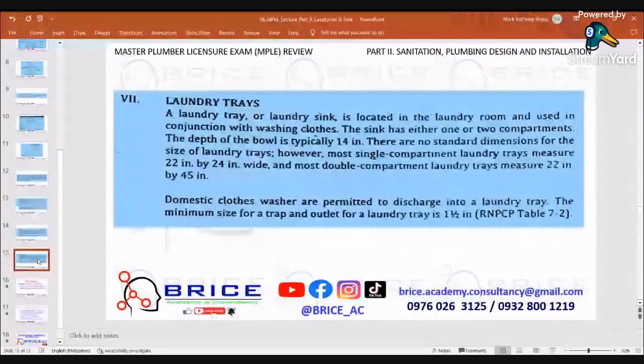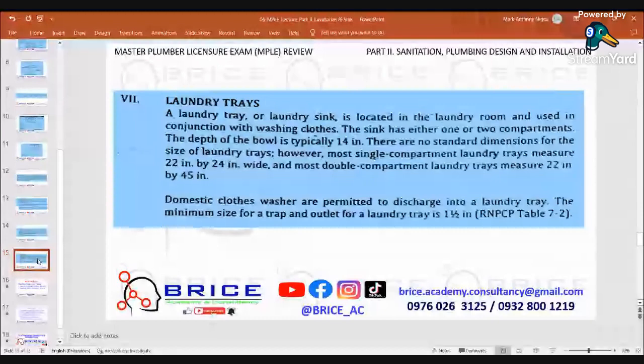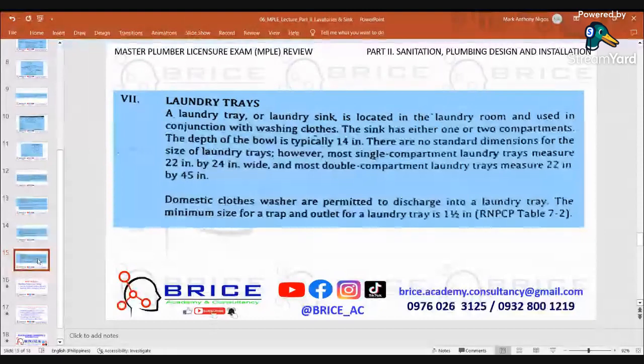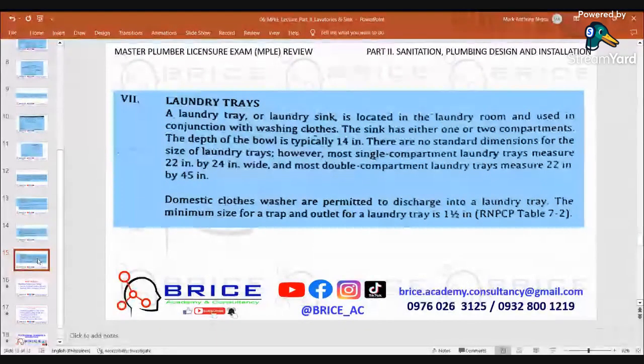The last topic for this session: laundry trays. A laundry tray or laundry sink is located in the laundry room and is used in conjunction with washing clothes. The sink has either one or two compartments; the depth of the bowl is typically 14 inches. Most single compartment laundry trays measure 23 by 24 inches or 22 by 24 inches wide. Most double compartment laundry trays measure 22 inches by 25 by 45 inches. Domestic clothes washer are permitted to discharge into a laundry tray. The minimum size for a trap and outlet is 1.5 inches — per RNPCP Table 7-2.